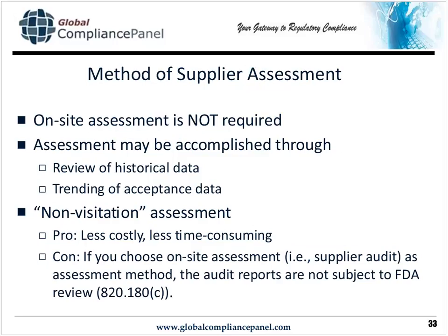You don't have to go to a supplier to monitor their performance. You can look at historical data. You can look at merely acceptance data, and you can make your conclusion that way. There's a pro and a con with regard to the non-visitation assessment. Obviously, if you're able to do this in documentation, it costs less and it takes less time. However, if you choose to go to the supplier, it becomes a supplier audit. Supplier audits are not subject to FDA review. So in that case, you would merely prepare a certification that says, on this date, I went to the supplier, and here's what I looked at, and you would sign that, and that would be verification to FDA to show that you performed this supplier audit.